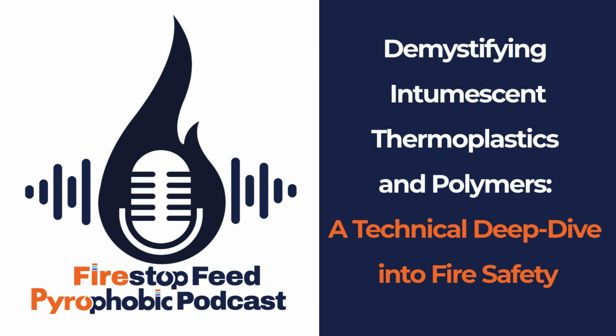Extremely dangerous. So how does the intumescent cap help there? Imagine an injection molded cap made from an intumescent thermoplastic that wraps around the busbar connection. According to the material, it offers several layers of defense. First, it has high dielectric strength, resisting electrical current flow and helping prevent the arc in the first place.